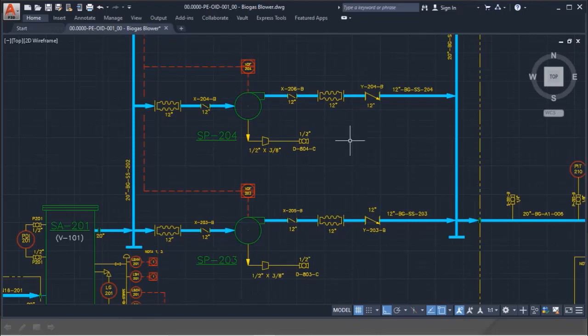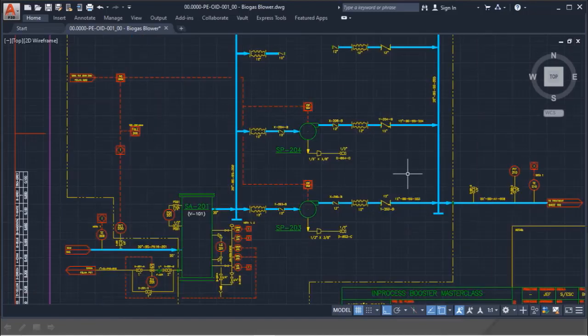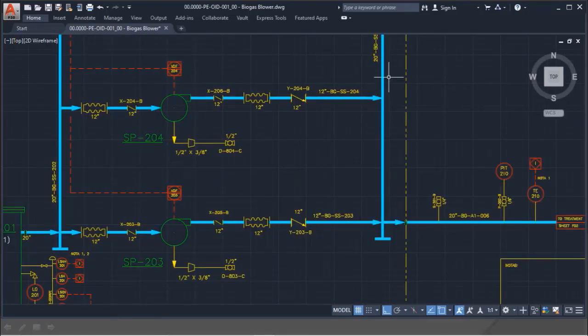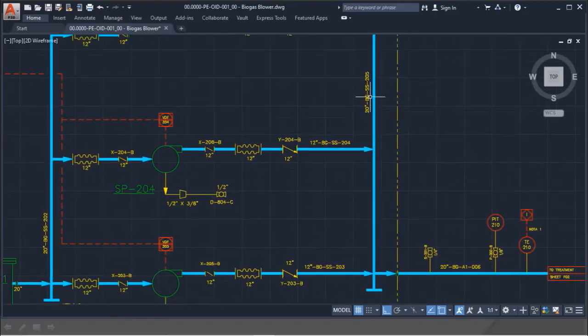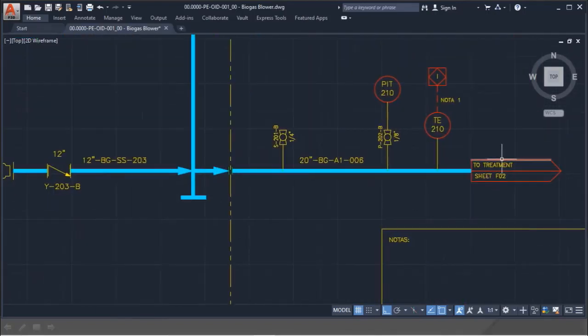As it is a dynamic equipment, it has vibration, so to not propagate the vibration to the piping, we have expansion joints here. This represents an expansion joint, and we have equipment running in parallel, so we need a check valve to prevent backflow from one blower to another. And once we have the gas compressed, it returns to a header of 20 inches and goes to the treatment unit. And we have a sample valve here, another pressure indicator transmitter, and the temperature measurement again.